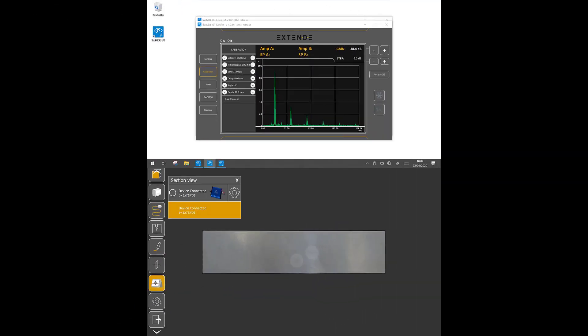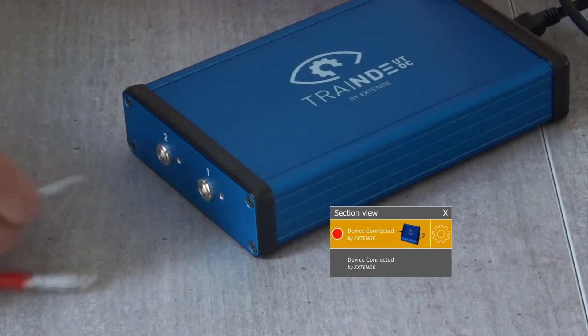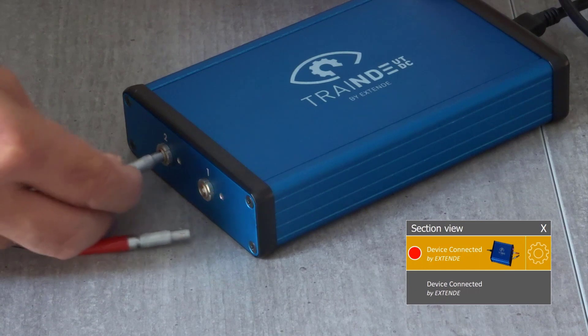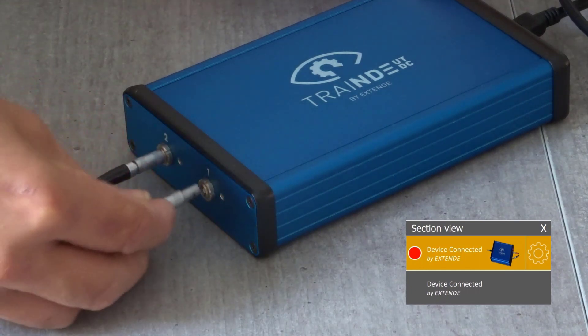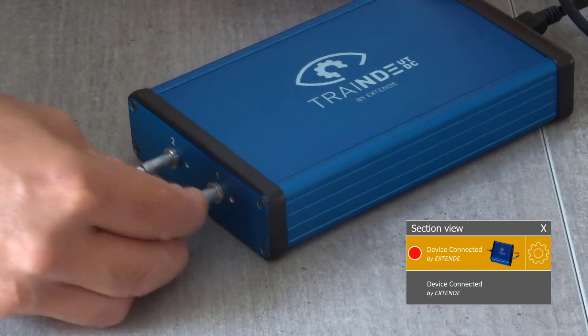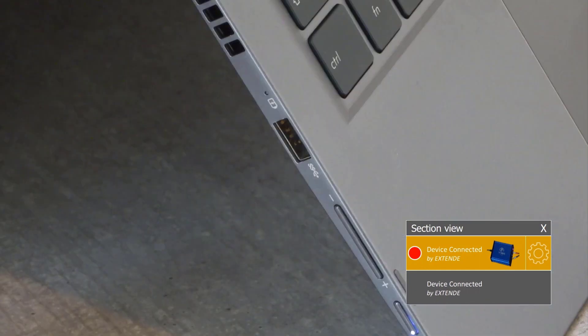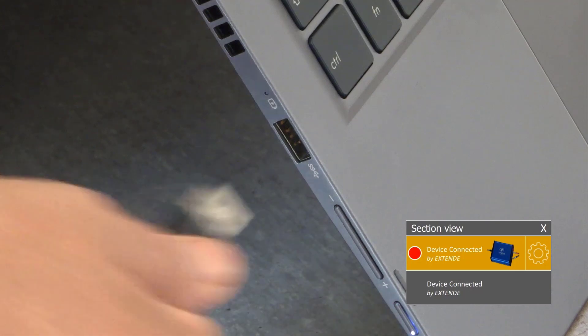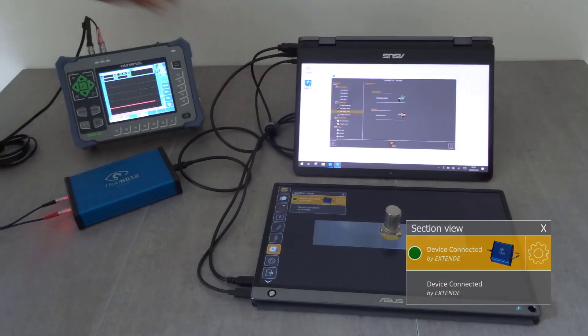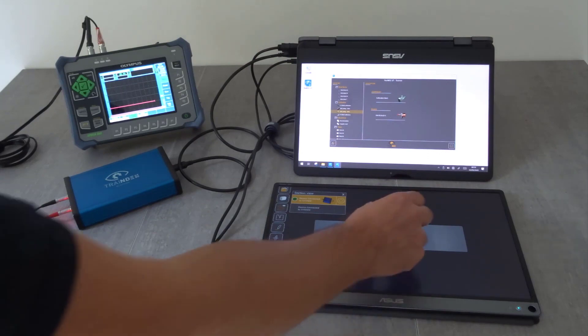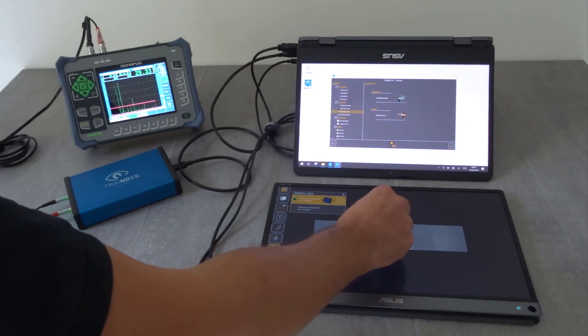TRAINDE UT device connected allows you to go further by plugging TRAINDE UT into your actual flaw detectors. This electronic device is plugged into the computer running TRAINDE UT through USB and to any flaw detector through LEMO. The analog signal at the location of the dummy probe is generated on the LEMO output and displayed on the flaw detector.